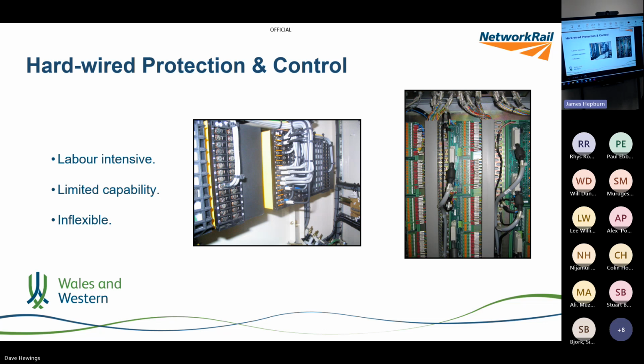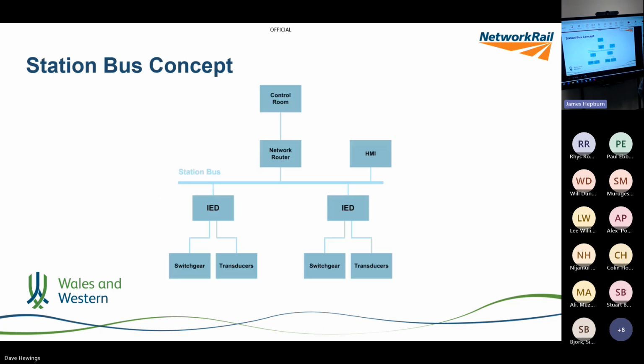How do you do that? Well, you replace what used to be protection relays by something called IEDs - that's the standard that came up with that name, not me - unfortunately, intelligent electronic device. And then you run effectively a data bus through the substation.